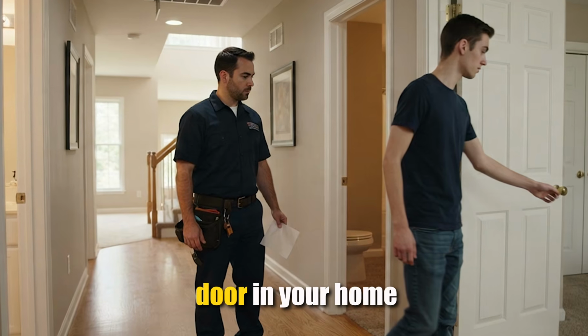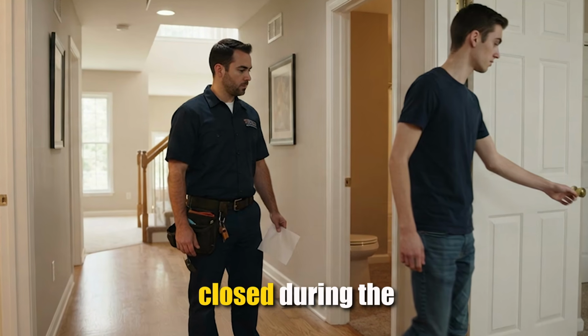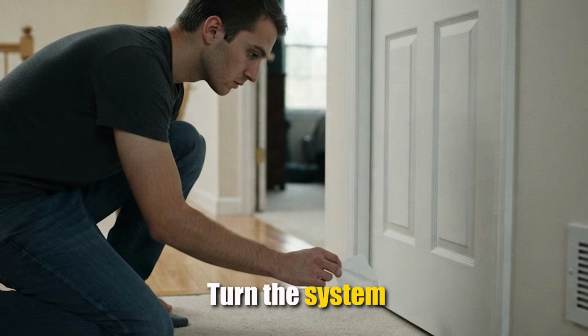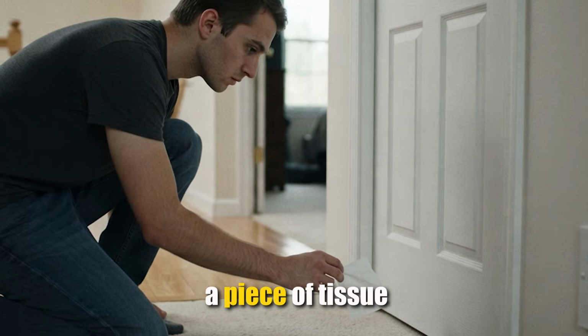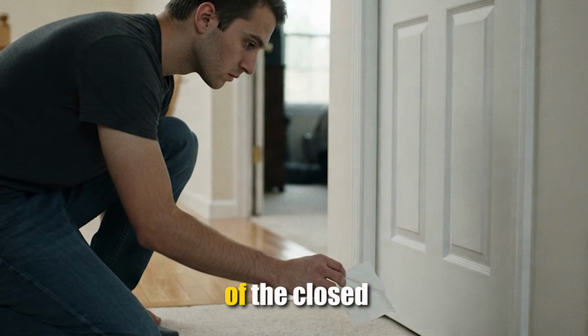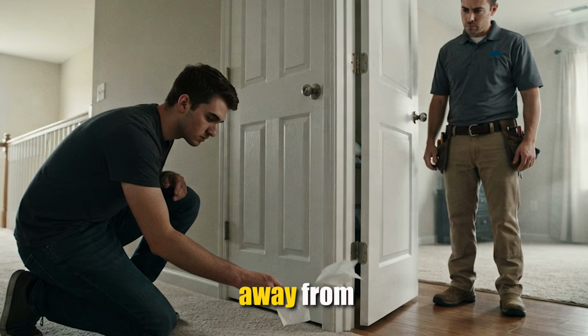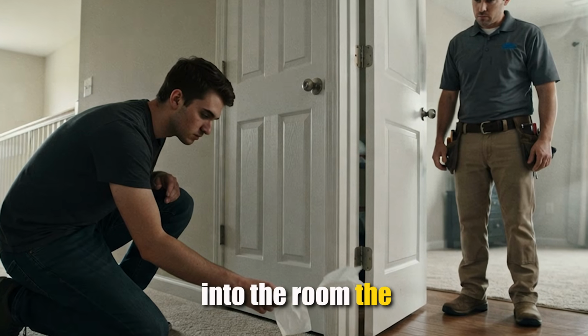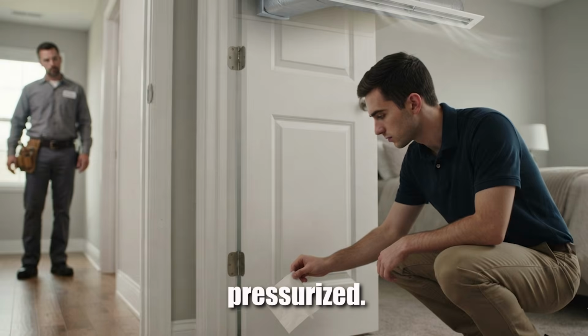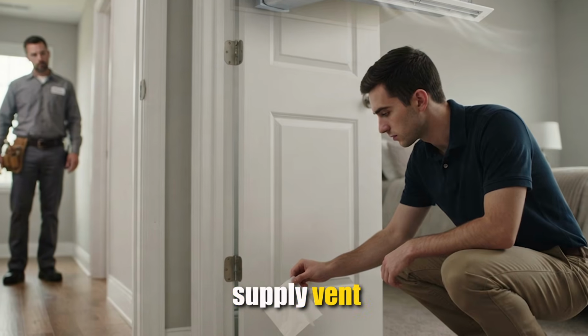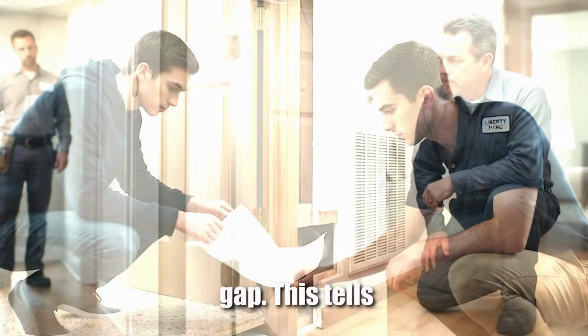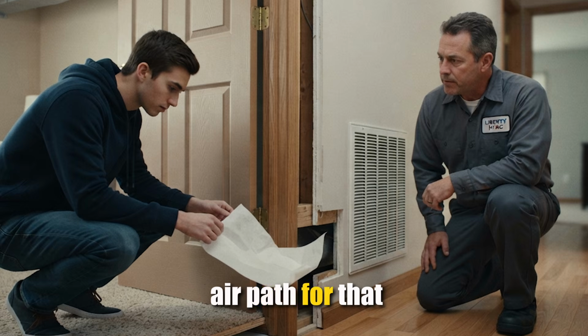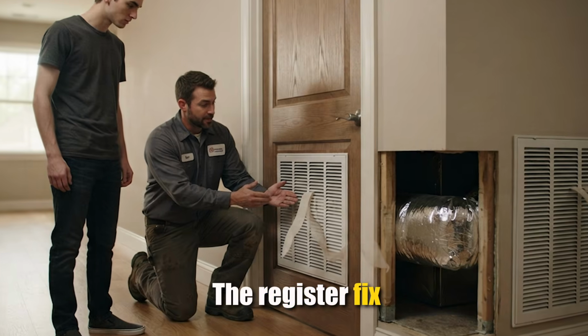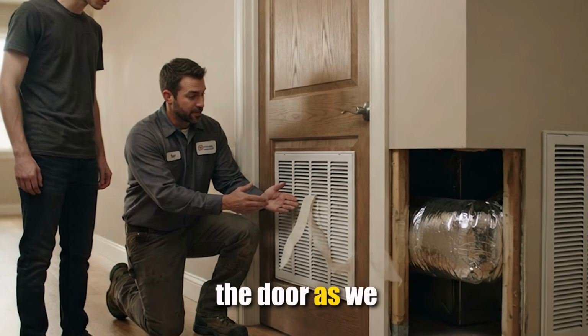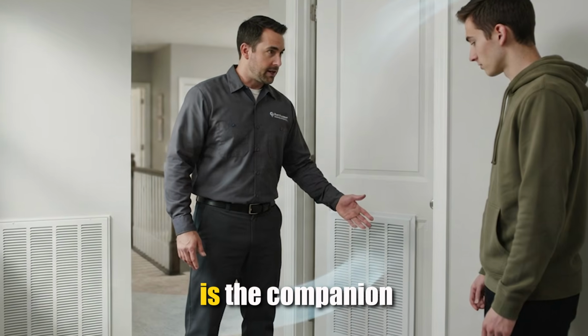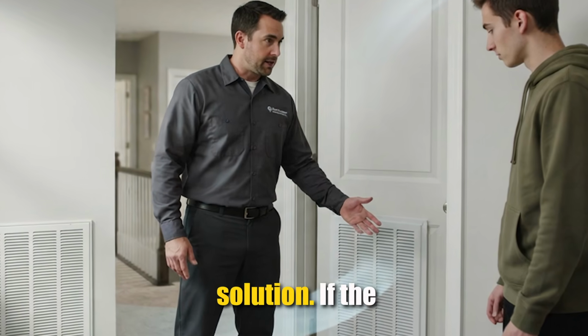Close every interior door in your home the way it would normally be closed during the day or night. Turn the system on, go to your hot room and hold a piece of tissue paper near the gap at the bottom of the closed door. If the tissue pushes away from the door, the room is positively pressurized. More air is coming in through the supply vent than can leave through the door gap. This tells you the return air path for that room is inadequate. The register fix helps here, but a transfer grill in the door, as we covered in a previous video, is the companion fix that completes the solution.